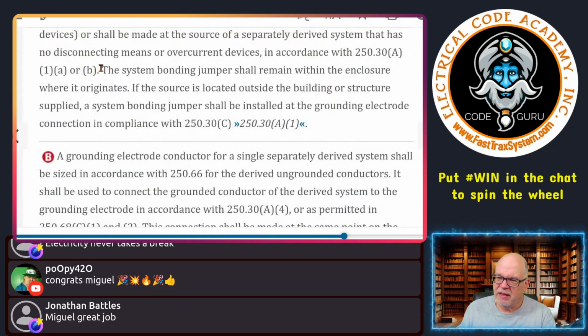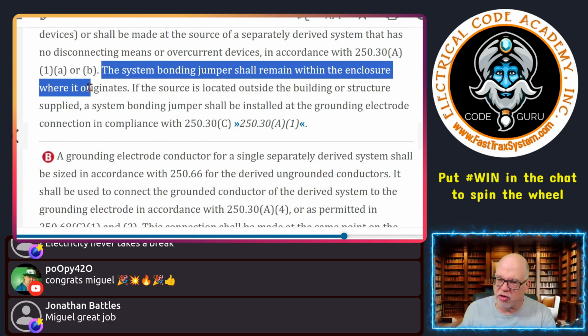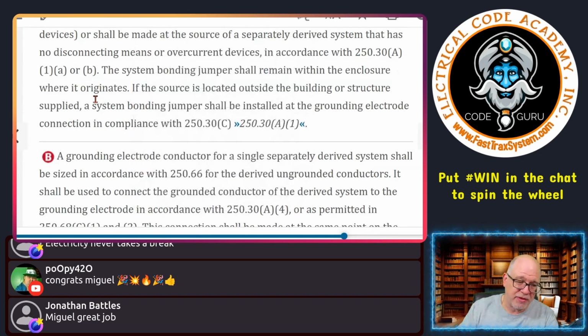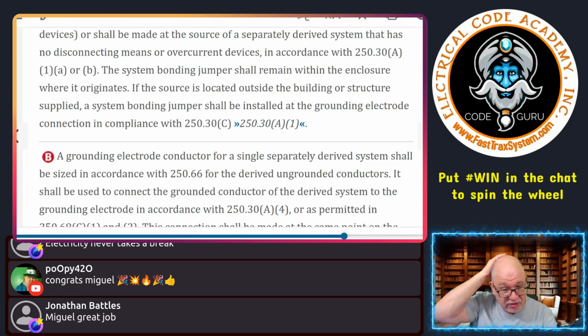Okay, now, it says the system bonding jumper shall remain within the enclosure where it originates. Okay, that makes sense. So wherever I put the system bonding jumper in, it stays there. Well, that's a no-brainer, wherever you put it. So if you put it from the XO to case in the transformer, that's done. If you put it in the first panel, that's where it's done, okay?